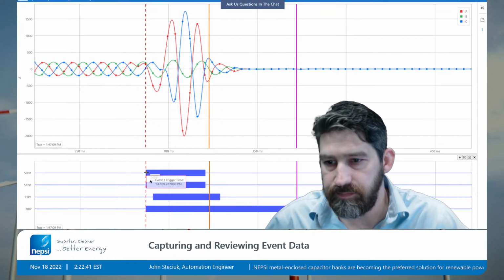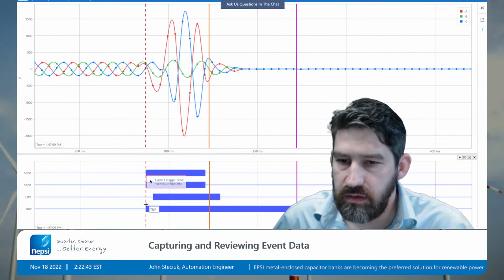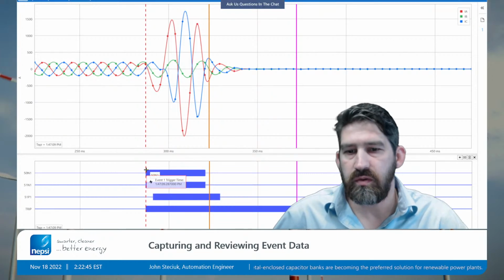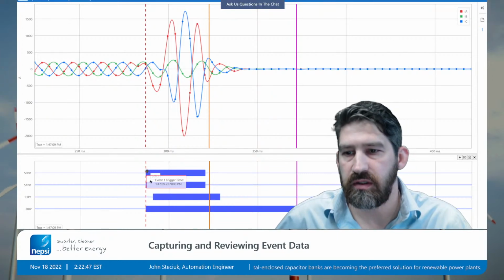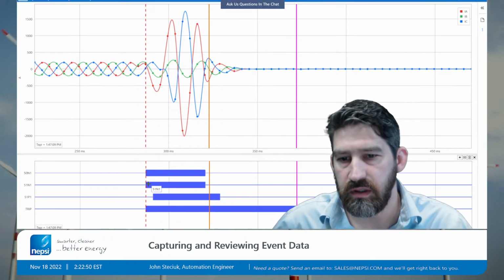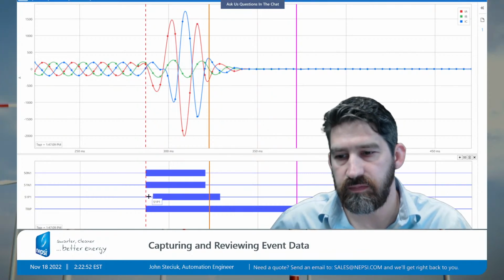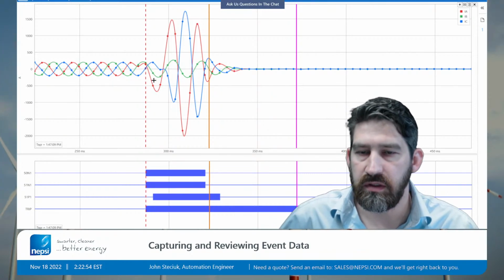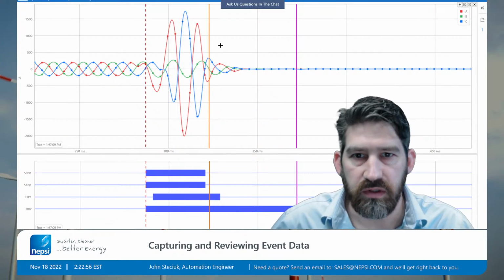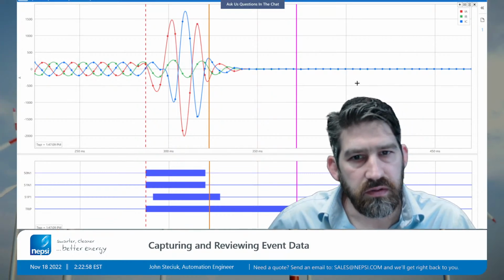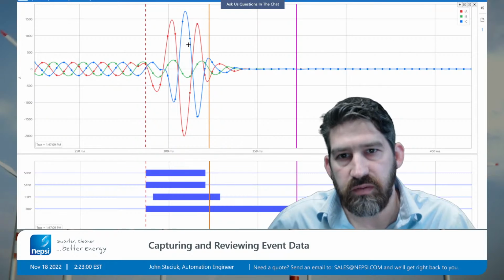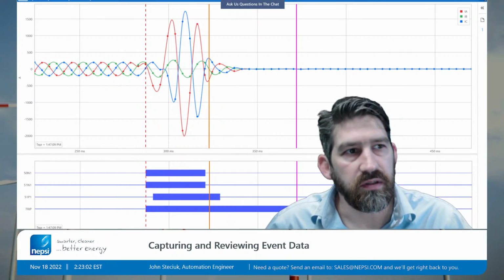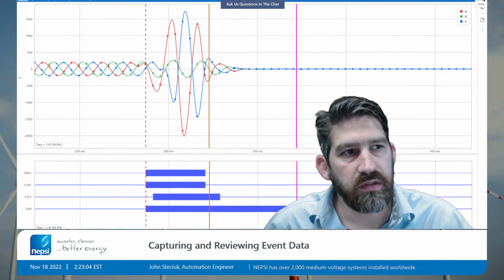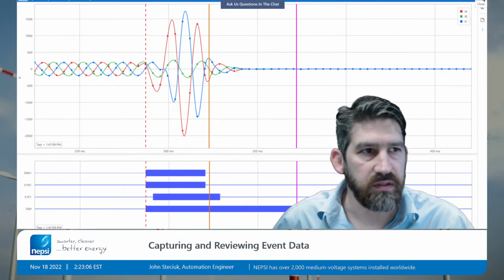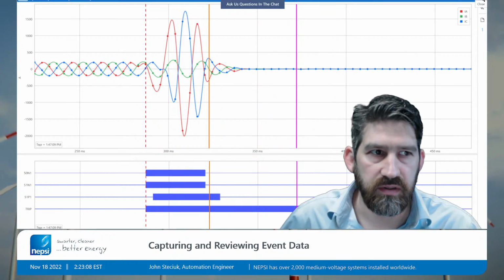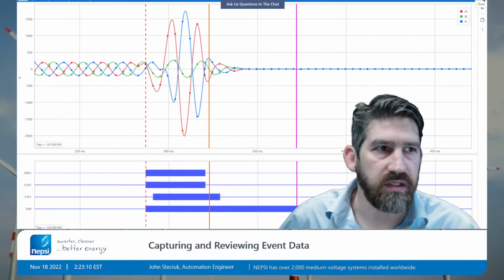We had a few alarms pick up here: neutral over current, neutral time over current, and time over current. So it gives you a pretty good picture of what happened. Maybe not the cause, but it at least gives you a place to start investigating.